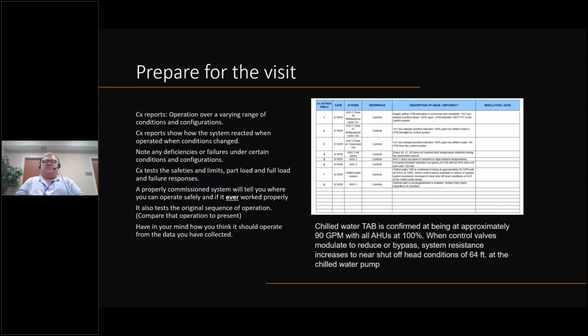In this project, I highlighted this comment I made: chilled water TAB confirmed at approximately 90 GPM with all the air handlers at 100%. When the control valves modulate to reduce flow or bypass, the system resistance increased to near shut-off head, to where you were actually deadheading or shutting off the flow of the pumps at 64 feet. So if you went wide open, you're fine, but once the valve started to control, it basically shut down the flow.